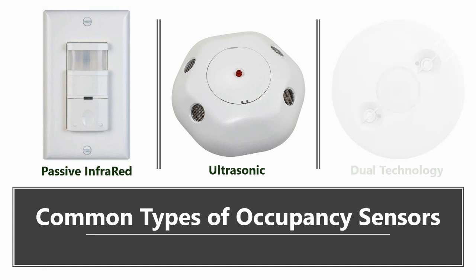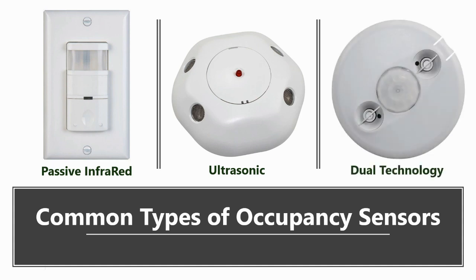The third type is a combination of both, or dual technology. Dual tech sensors utilize two detection methods to increase reliability in applications where a higher degree of detection is desirable, such as classrooms. Most manufacturers offer sensors that combine ultrasonic and passive infrared technologies. They activate only when both technologies detect the presence of people, but only one technology is needed to hold them on.